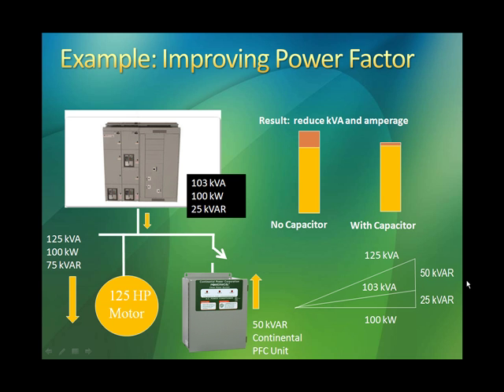of 75. Now you say, wow, you dropped the kVAR by 2/3, but you dropped the kVA by a lot more than 2/3. Well, if you notice that, you're absolutely right. This is a geometric relationship. Take a look in the bottom right-hand corner of your screen, and you'll see what I'm talking about. Without the PowerWorks engaged, you see the numbers there: 125 kVA, 75 kVAR, and 100 kW. When we drop the kVAR from 75 to 25, we increase the power factor significantly, and now that vector for the kVA is much, much shorter. Now it's 103 kVA instead of 125.